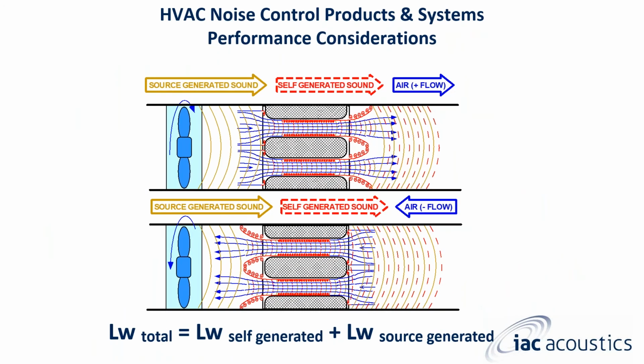Here's another pictorial of self-generated sound coming from the fan, on the top for forward flow. You can see where noise can be an issue. At the same time, down at the bottom, you see self-generated sound, again with air pulling in and the noise going in reverse. And again, you can see where the noise is, in between the silencer and the fan instead of after the fan.